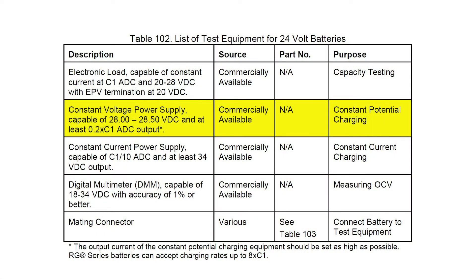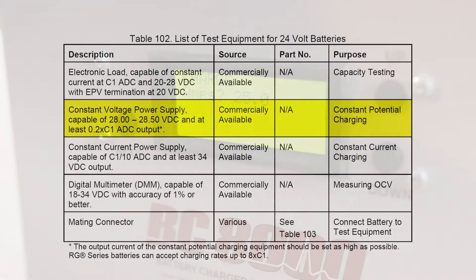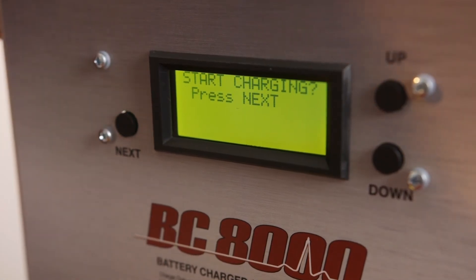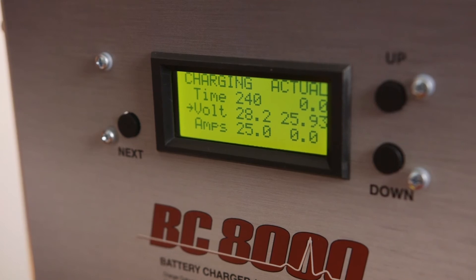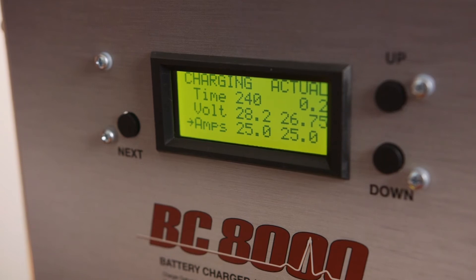Per Table 102 of the CMM, the current needs to be at least 20% of the C1 rate. For this battery, the C1 rate is 42 amps, so the charge current needs to be at least 20% of 42, or 8.4 amps. However, it is best to use the maximum output of 25 amps to cut down on charging time. With these settings in place, we can now start the charge cycle. As you can see, the battery is charging at a voltage level above 24 volts and a current of 25 amps. Once the battery voltage reaches 28.2 volts, the voltage will be held constant at this value, and the current will taper down to a very low level. We'll come back in 4 hours when the charging cycle is complete.